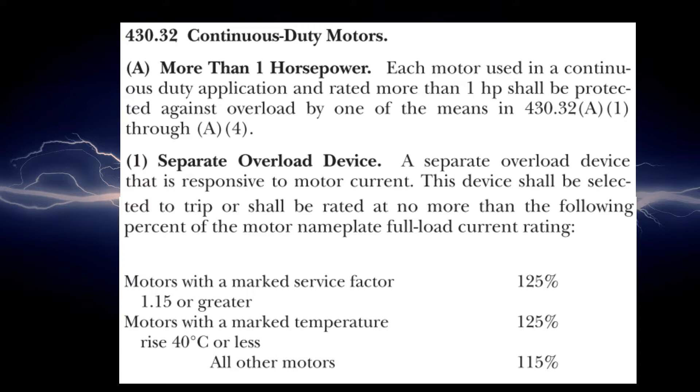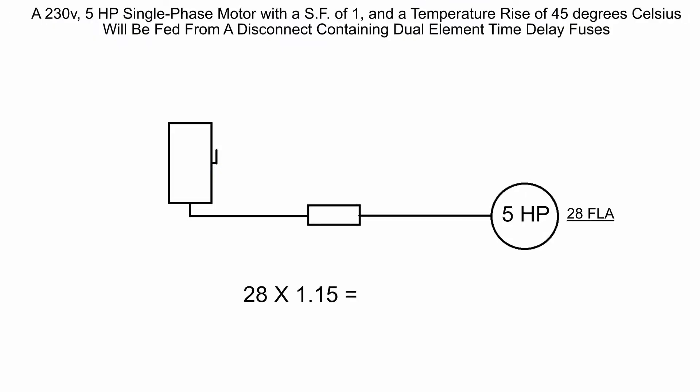It says motors with a marked service factor of 1.15 or greater would have 125 percent. However, we have a service factor of 1, so we don't qualify here. It also says motors with a marked temperature rise of 40 degrees Celsius or less is 125 percent. We have 45 degrees Celsius, so we don't qualify for these. We're going to be in the all other motor section at 115 percent. We'll take the full load amps of 28 times 115 percent or 1.15, which is going to give us 32.2 amps.